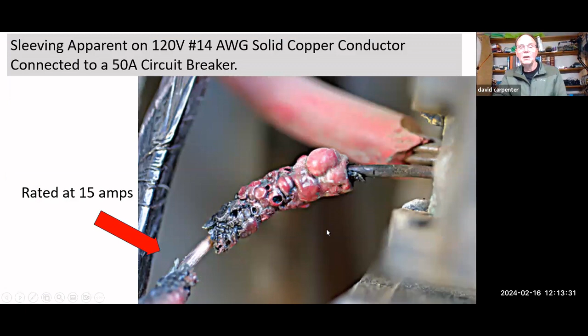Here's another one - they got the wrong size wire. This wire is for a 50-amp breaker, and this wire here is designed for a 15-amp breaker. They've tied them together under a 50-amp breaker. You can't do that.